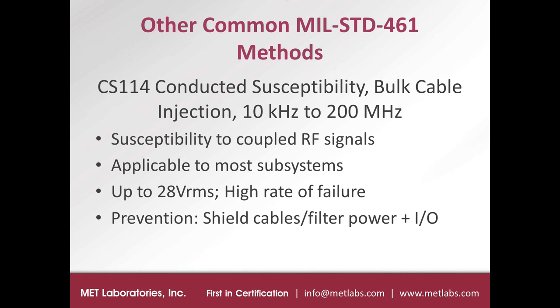And the test level is actually given in dB microamps, and that can be a type of unit that's not very familiar to a lot of people, so converted to volts in a 50-ohm system, that could be up to 28 volts RMS. The highest test level of any of the curves for the test is actually 109 dB microamps, which would only translate to 14 volts RMS in a 50-ohm system. However, part of the procedure only allows you to limit the coupled signal to 6 dB higher than the test level. So once you're allowing something 6 dB higher, you could be coupling up to 28 volts RMS signals onto the EUT cables.